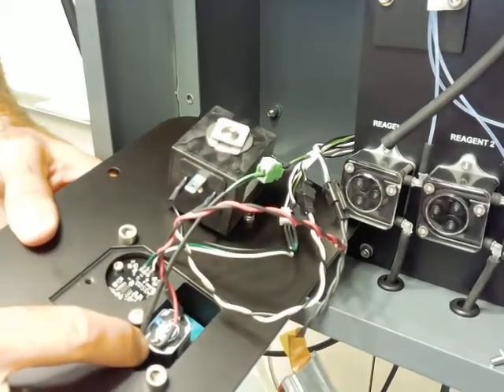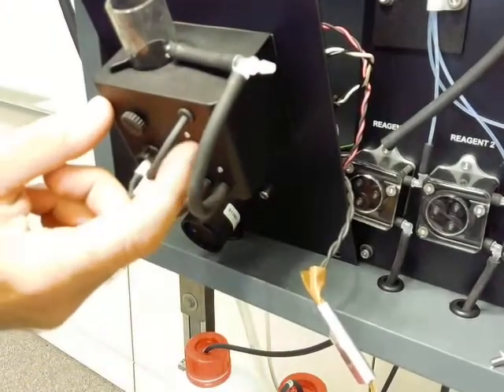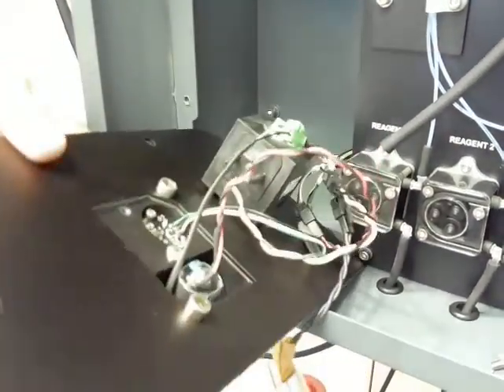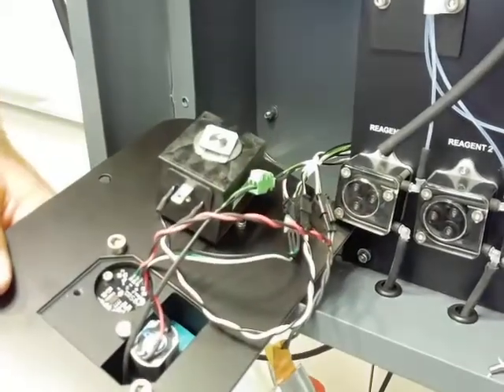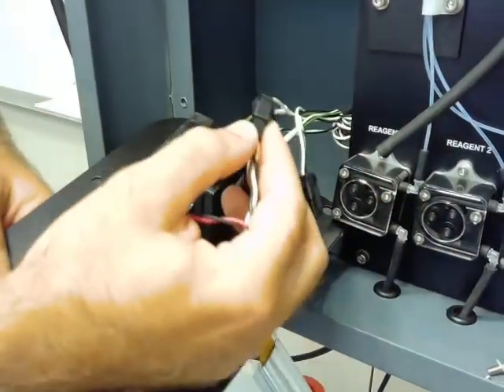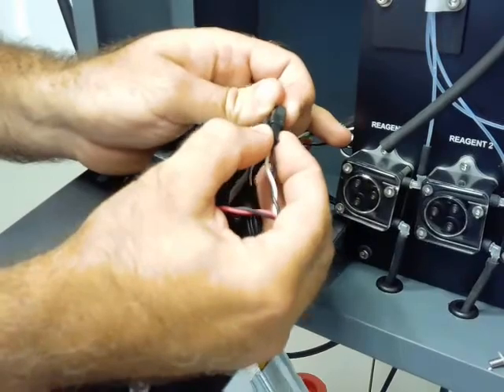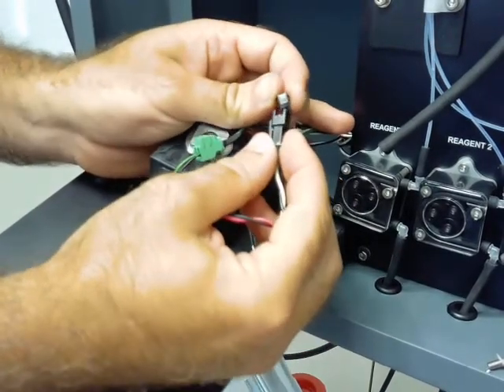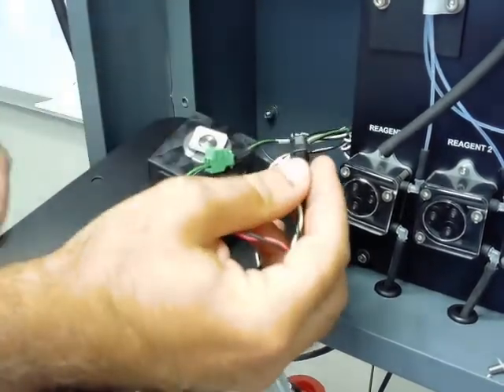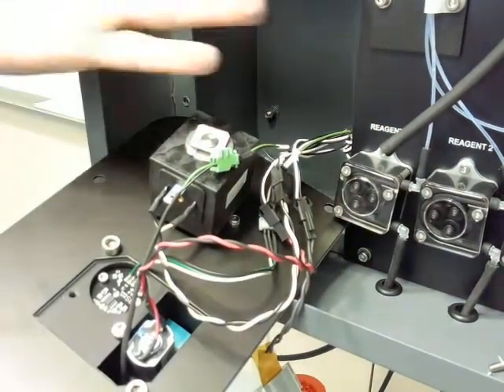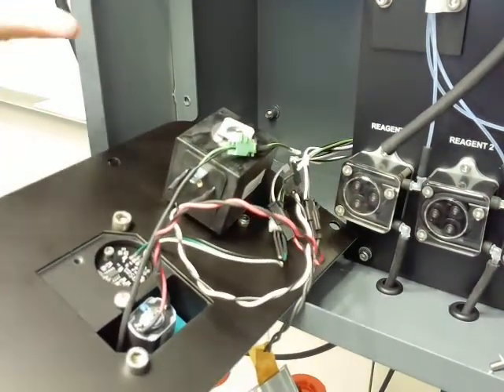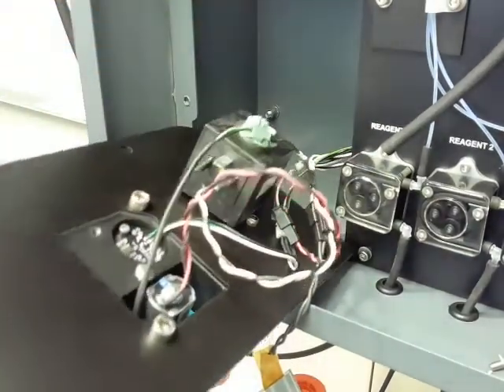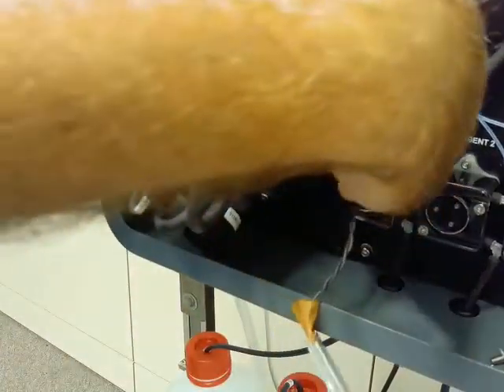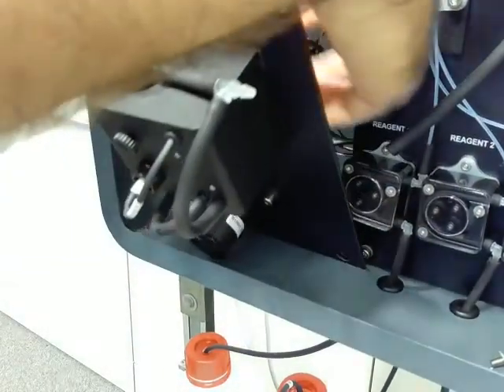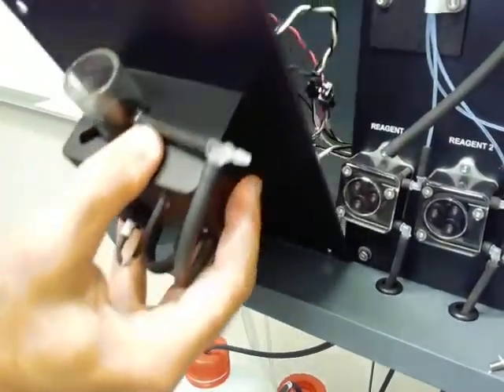And then right here we have our mixing pump, a little diaphragm pump. To remove that, we would loosen the screws on the front side first, then pull it out the back, and replace it with the new one. All these components back here have little quick disconnect connectors for the electrical side, so they're nice and easy to remove. The only other thing going on behind the panel is these connections and the pump motors on the other side, so no sample should be back there to cause any problems.